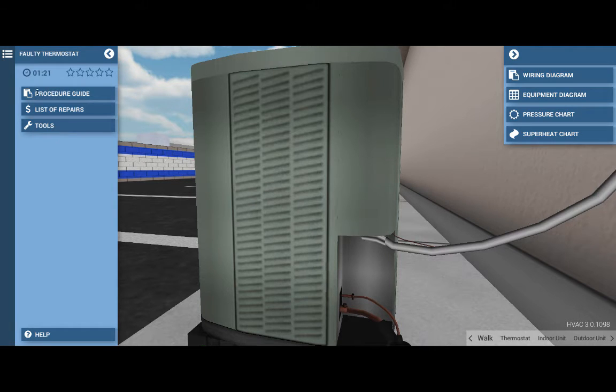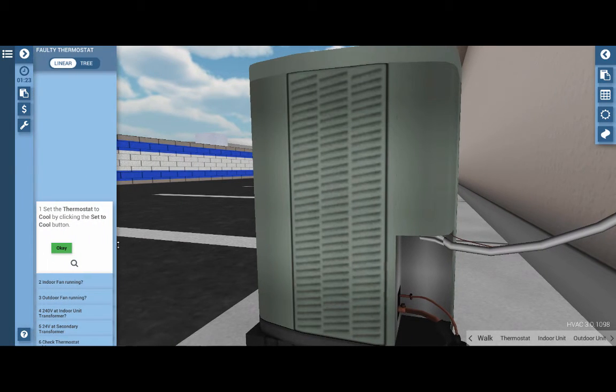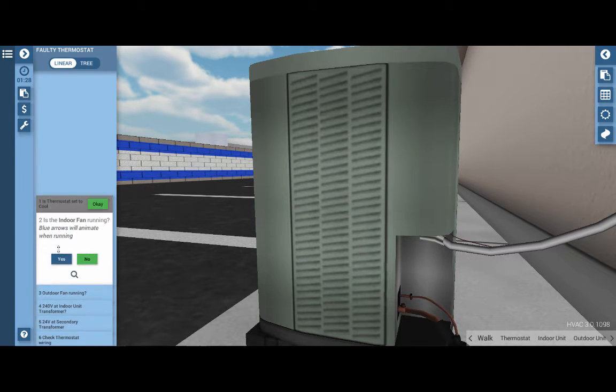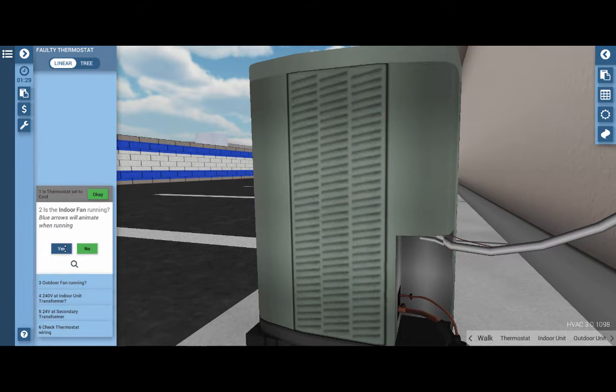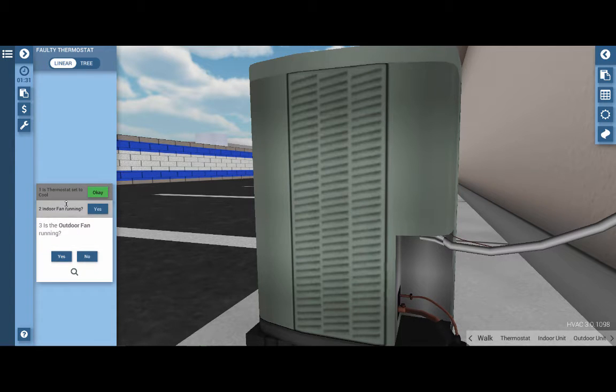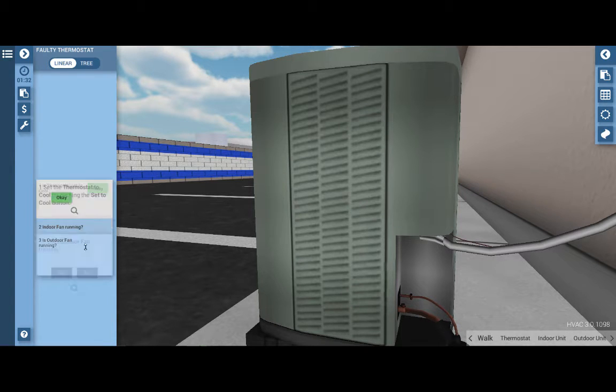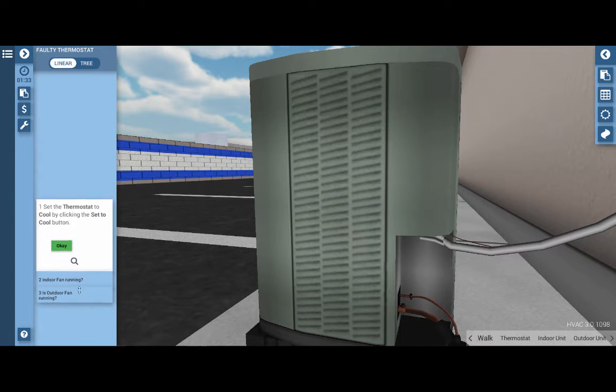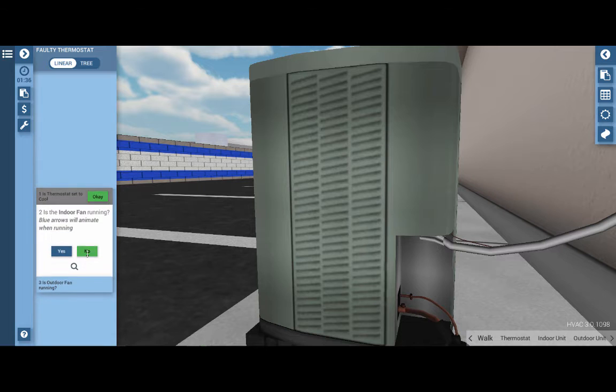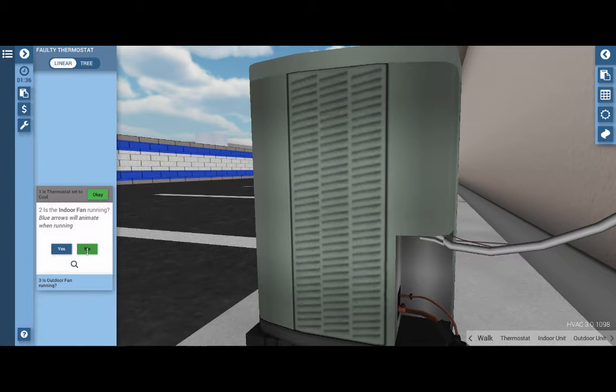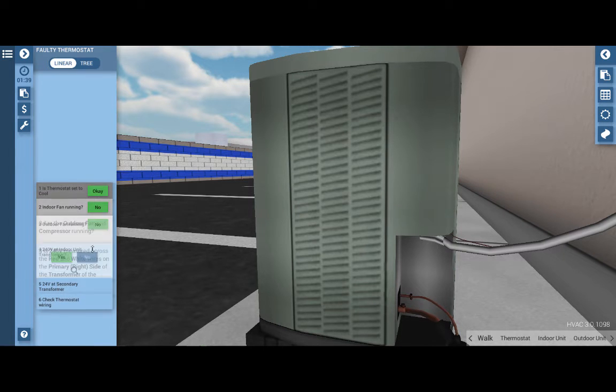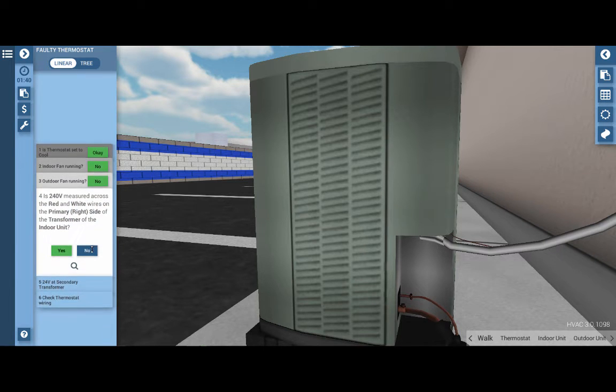At this point, my suggestion to you is to use the procedure guide here at the top left, which will walk you through each step in this troubleshooting procedure. We've completed step one, two, and three. Our indoor fan is not running. Our outdoor fan is not running, nor is our compressor running.